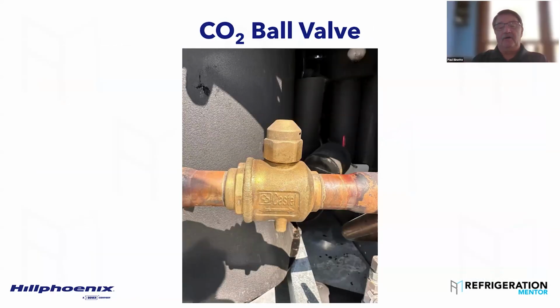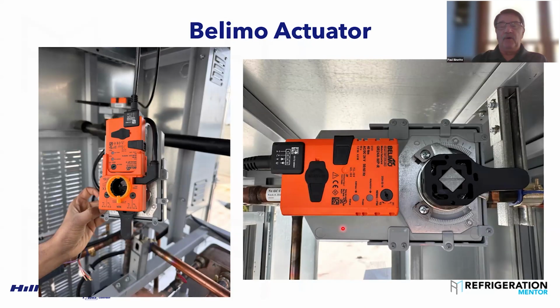And well, also on another note on the Belimos, if you have a hot gas defrost system, we had a Belimo for the hot gas supply line, an ICAD for the pressure control, and then your inlet header was another modulating valve. We found the modulating valve on the header moved slower than the Belimo did, and we were deadheading for the first 5 seconds because our pressure was going up too quick on our hot gas.